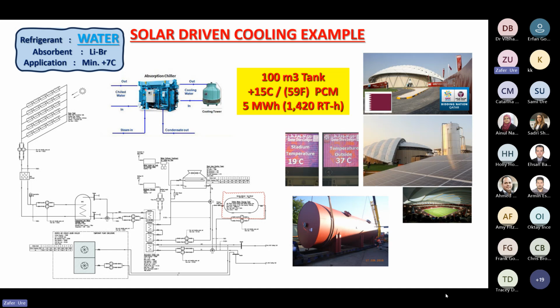Lithium bromide is the most common workhorse of heat-driven absorption. The working absorbent is lithium bromide salt, but the refrigerant is water, which limits its ability to produce cold water no lower than 7 degrees C. That's the limit for water absorption machines, so they lend themselves to simple air conditioning or chilled/cooling applications down to about 7 degrees C chilled water.